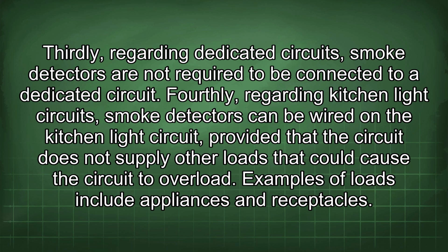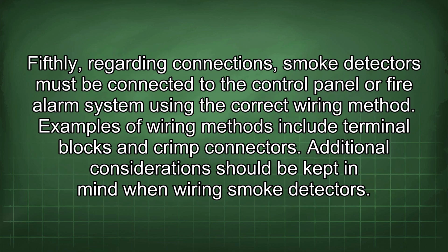Fourthly, regarding kitchen light circuits, smoke detectors can be wired on the kitchen light circuit, provided that the circuit does not supply other loads that could cause the circuit to overload. Examples of loads include appliances and receptacles. Fifthly, regarding connections, smoke detectors must be connected to the control panel or fire alarm system using the correct wiring method. Examples of wiring methods include terminal blocks and crimp connectors.